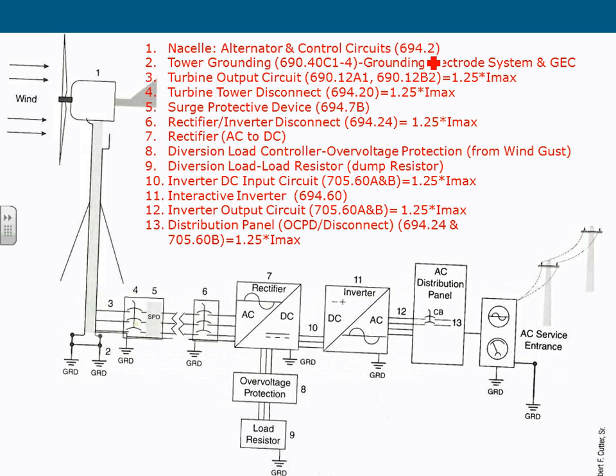So your disconnect, number 4, how do you size the disconnect? Remember that 1.25, that magic number that worked for everything else? You take the I maximum. The way they get the I maximum, say your turbine is 7.5 kW, and your voltage is 3-phase 220. So you take the kW divided by 1.73 times 220, assign a 0.9 for power factor, you find the amps of that turbine, you multiply by 1.25, and you size the conductor.